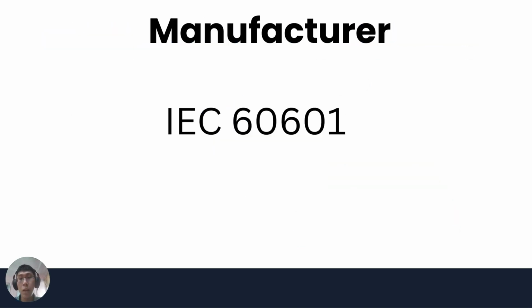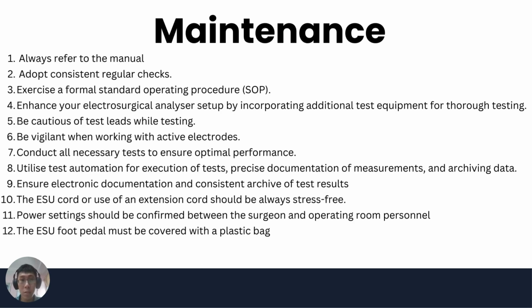Good practices. Manufacturers should practice conformity to the IEC 60601 basic safety and essential performance requirements of medical electrical devices. Good maintenance practices. Firstly, always refer to the manual. A user manual should be received from the manufacturer and be readily available in the practice setting. Instructions for use should be kept together with the ESU.